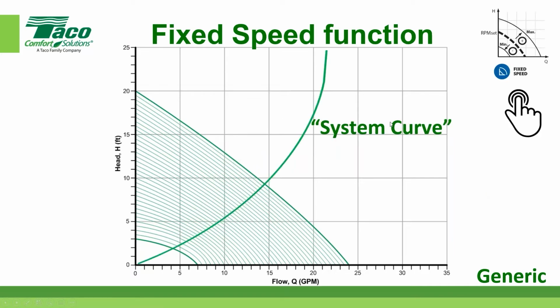So let's show you a system curve laid on top of all the circulator performance curves and the various RPM reductions. If I'm running at maximum speed, this is my operating point. As I manually turn it down, I want you to understand what's happening here. Notice I've just chosen a lower RPM, and I can turn it down again and again, choosing these subsequent lower RPMs. That would be a manual way of turning a high efficiency circulator down. Okay. Remember, they can do this automatically as well.